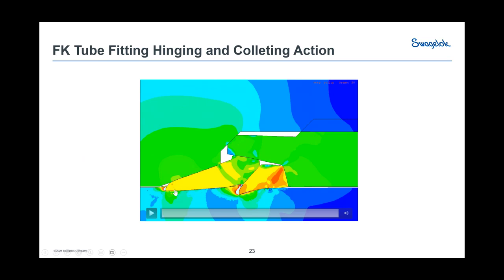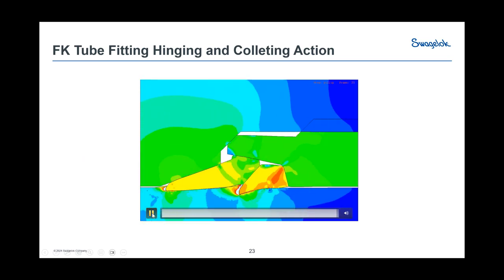But wait a second, it's doing something different. It's actually diving into the tube as well. What we found was in order to get the higher pressures, we have to use a different type of tubing, and it's called eighth hard tubing. Eighth hard tubing is different in multiple ways from instrument tubing. One of them is they don't control the OD of the tubing as well, often because it's used for things called cone and thread fittings. We'll show you that in a minute.